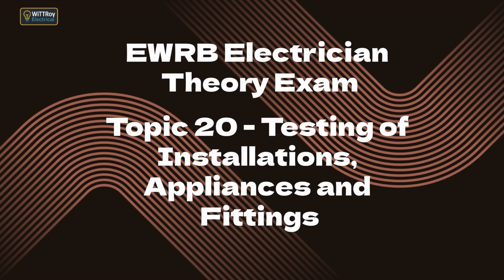Topic 20f. State that Regulation 70 specifies the installation work requiring inspection by a registered electrical inspector prior to connection to the power supply. Regulation 70 of the Electricity Safety Regulations lists the work that must be inspected by a registered electrical inspector before connection. This includes mains work, main switchboard work, meter board work, work in medical or hazardous locations, large capacity installations, and high-risk electrical work. The electrician cannot connect these installations, they must wait for inspection approval.